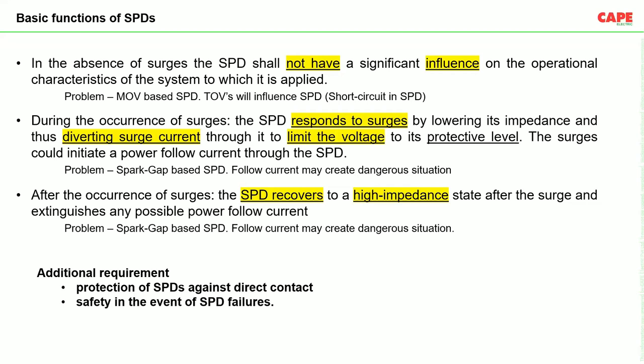Once an SPD fails in a short circuit mode, there is a short circuit current which flows from the power source through the SPD into the earth. Now, energy dissipation during the conduction of this short circuit current can be excessive and can cause a fire hazard. Hence, SPD manufacturers should ensure the safety in the event of SPD failure. This is what is explained in the standard 61643 part 12 as well.